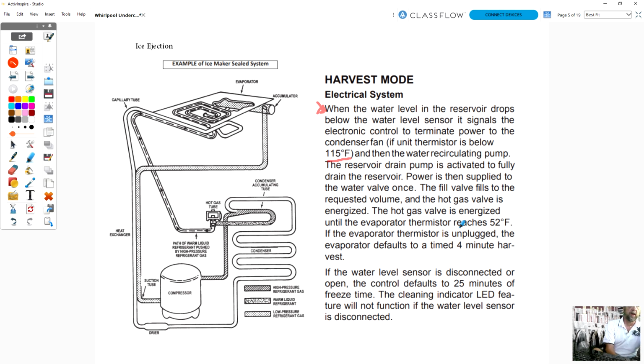The old design would just fill up till it overflowed, and hopefully it overflowed enough that we'd have fresh water. This particular unit, they added a separate drain valve. The older ones didn't have a drain valve, and it would pump out the water during the ice ejection cycle and then fill up with fresh water. And by doing that, that helped assure that all the old water that was inside that machine is removed.